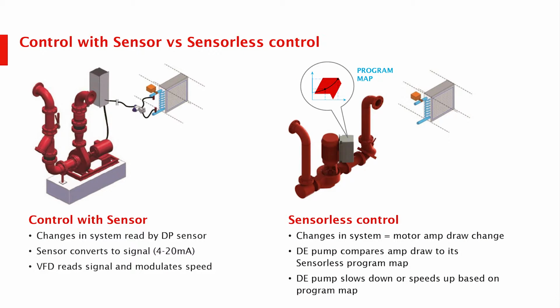Based on speed and power that we get from the drive, we calculate and present flow and head, and it's amazingly accurate. We've shipped over, it's not just about us, the industry has shipped over 50,000 units using this technology. So it's not brand new, and it typically depends on the slope of the curve, it's always within 5%, but depending on the actual interpolation, in many cases it's within 2% accuracy. So it gives you a reading that should be more than sufficient for most flow applications. Ultimately, it mimics the way a sensor would act in the field.